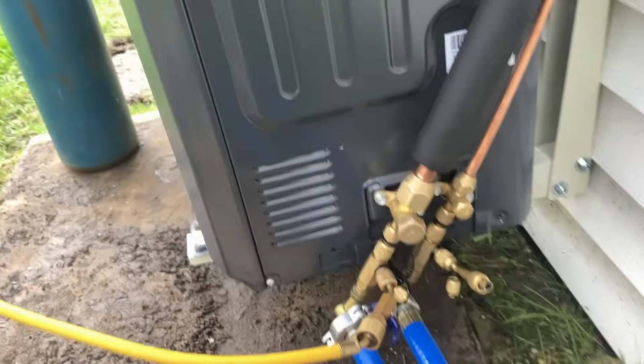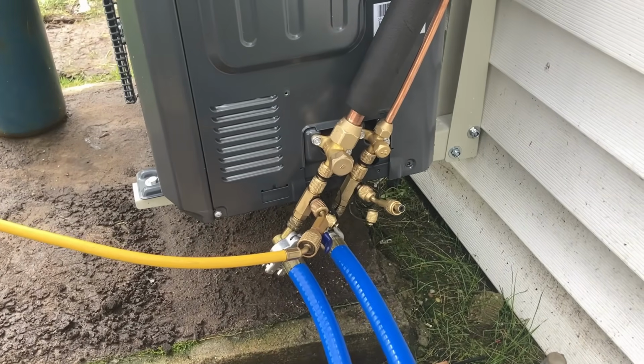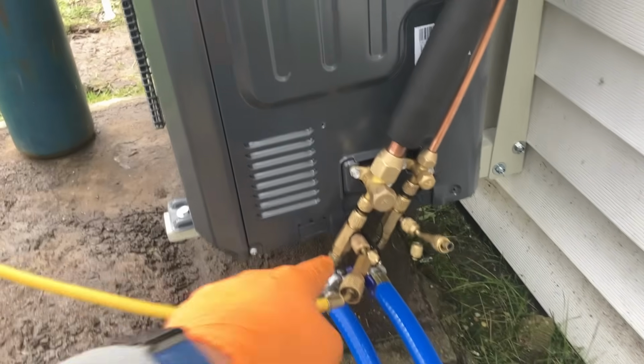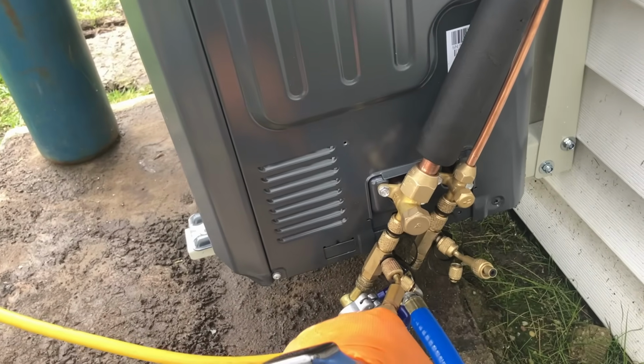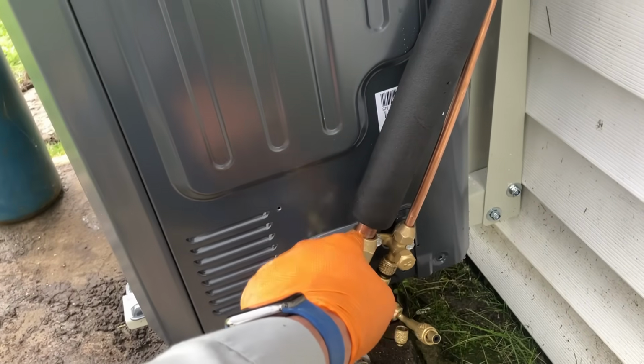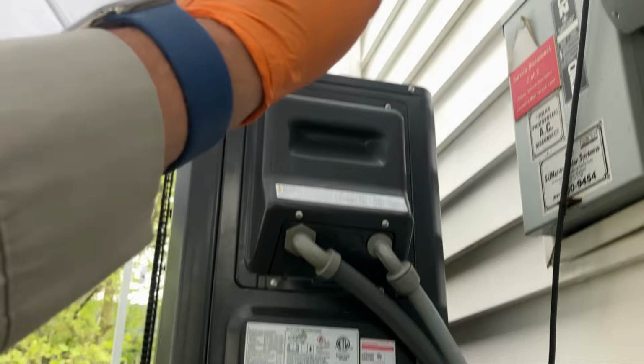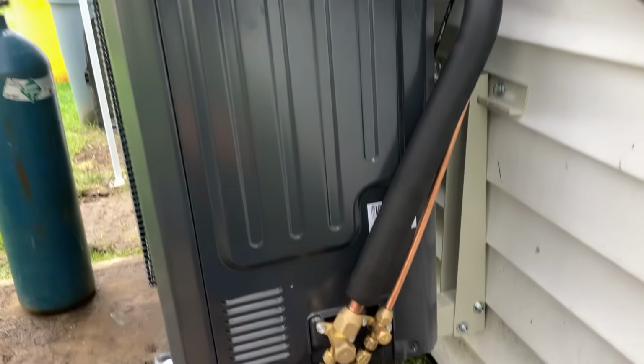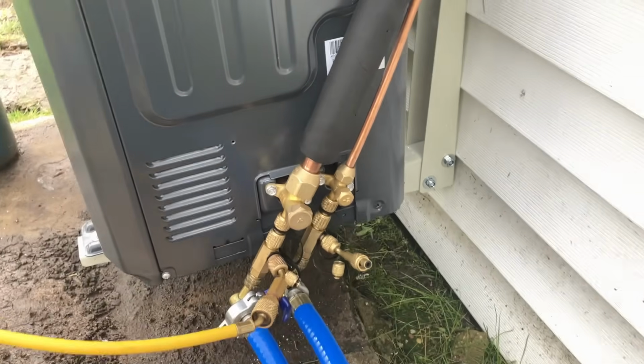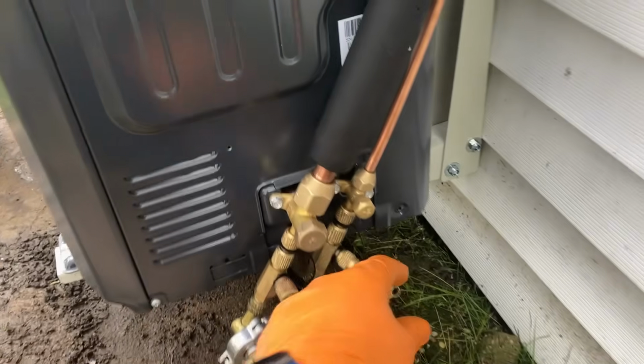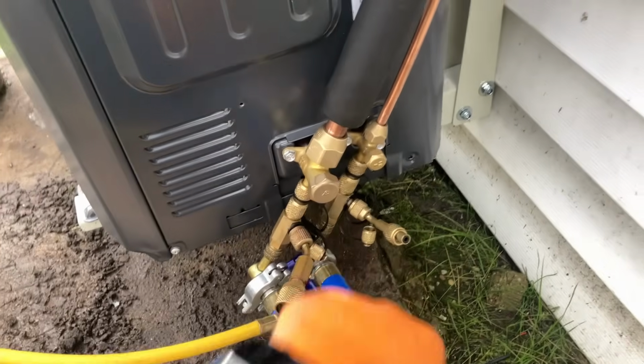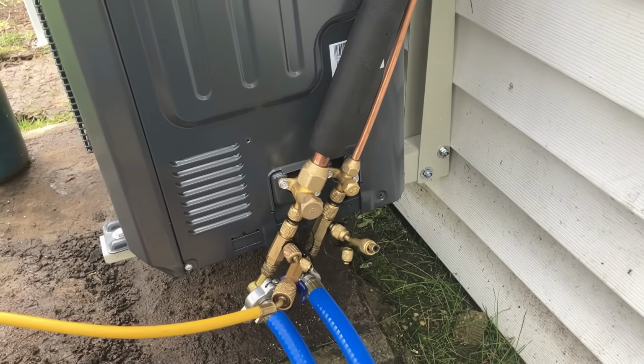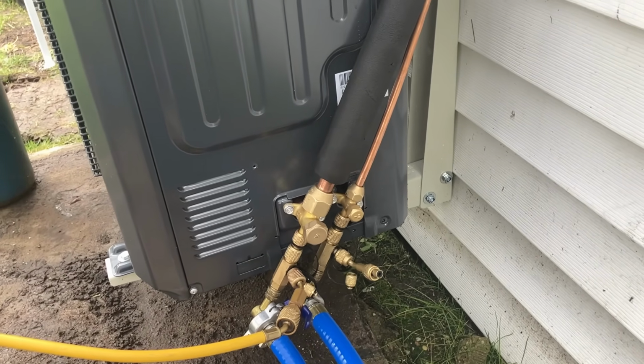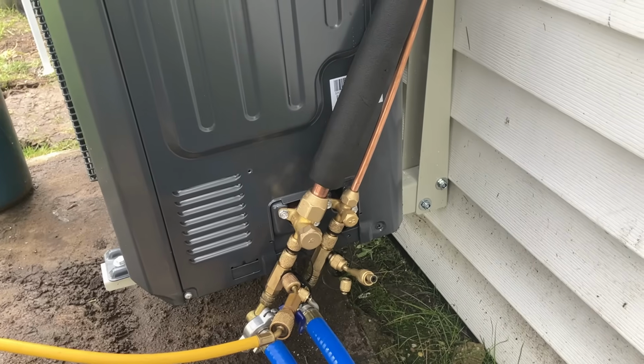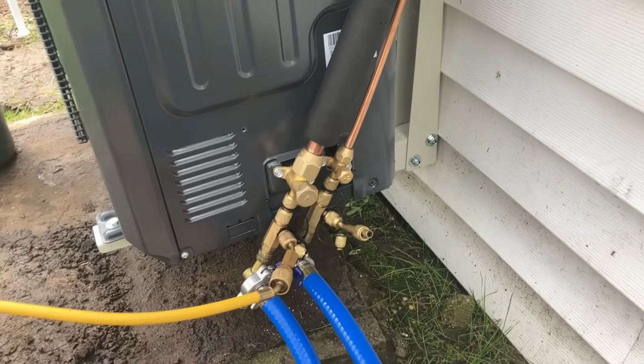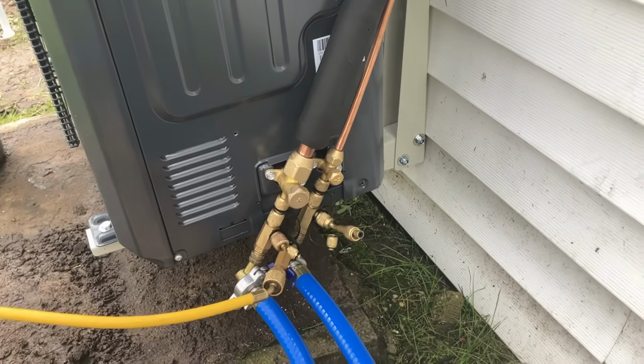Let's do a nitrogen purge through the system. So right now I have 400 psi of nitrogen going through my 3/4 that goes into my 7/8 to the evaporator and back here on the liquid line, being pushed out where my micron gauge was. It's going to push out any kind of moisture, non-condensables that are having a hard time getting out of the system. And this is called a nitrogen purge.